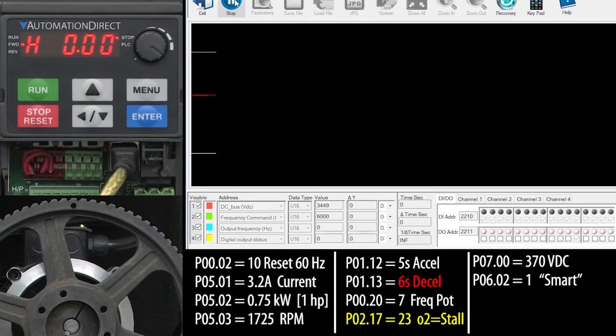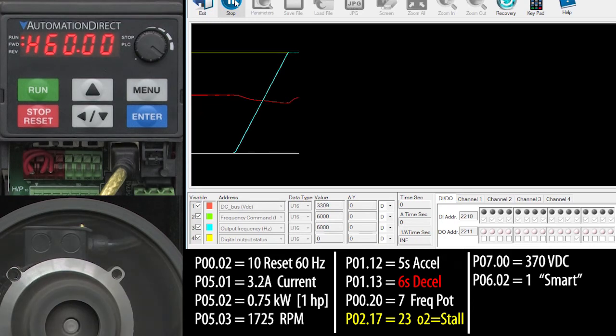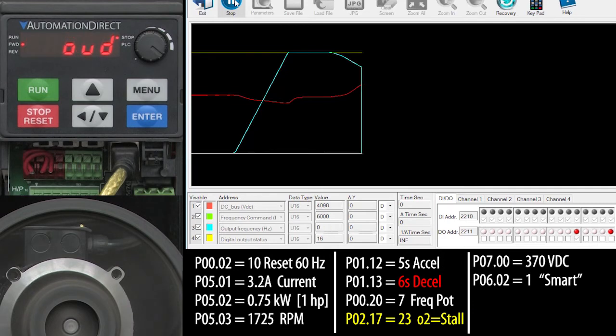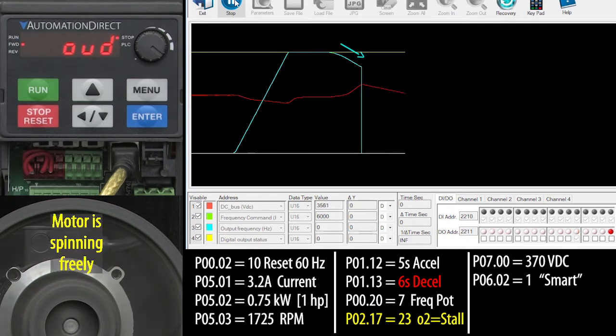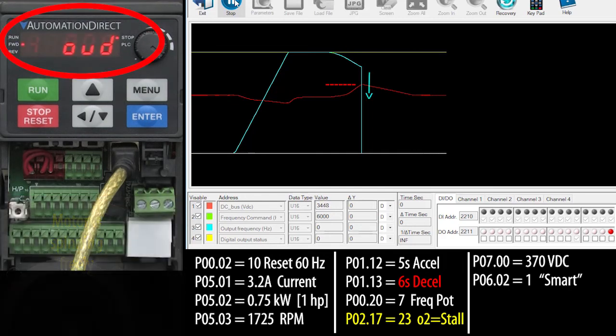I'll start to scope, hit run, wait for it to ramp up and for the DC bus to settle out and hit stop. Interesting. It looks like it tries to manage the deceleration and it does hold the fault off a little longer, but the DC bus still got too high and the drive eventually faulted out.